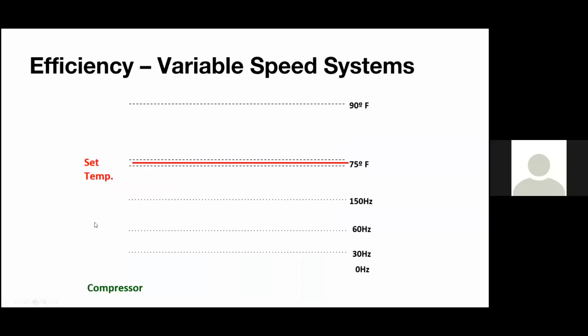In comparison, we're going to look at a variable speed system, or inverter-driven compressor technology, which is what is in heat pumps, right? So same kind of setup. We're going to have that set point at 75 degrees. We need cooling capacity, and we are going to turn on the compressor. And at that compressor, you can see it's not a steady line. It's actually a little jagged line, which is basically showing that we do have a soft start in the compressor. So it's not going to get the current right away. It's going to slowly work into it.